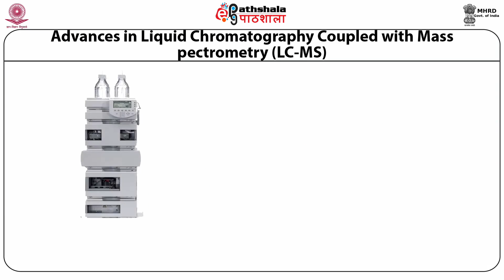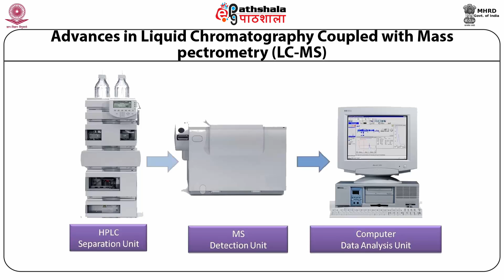An LC-MS system usually consists of three units. The first unit is the HPLC separation unit, the second unit is the MS detection unit, and the third unit is the computer data analysis unit. In the HPLC separation unit, the proteins or other samples which have to be analyzed are separated in HPLC. Once they are separated, they are sent to the mass spectrometer where their ionization occurs, and these molecules are separated on the basis of mass to charge ratio. Once they are separated and detected, they are sent to a computer which has software, and the data can be analyzed in this data analysis unit.